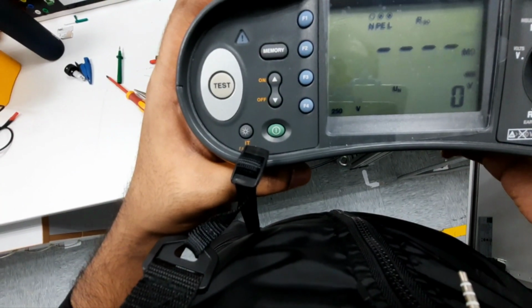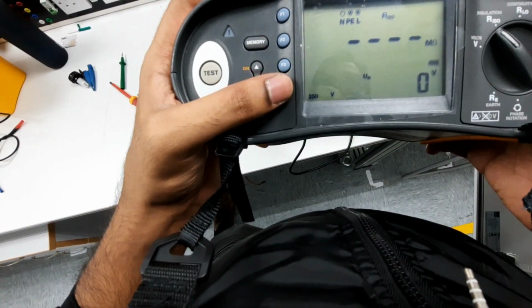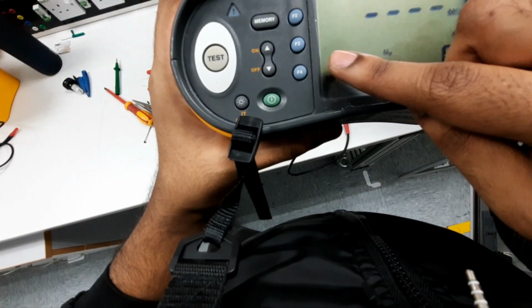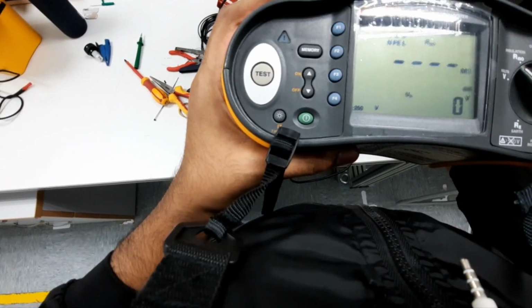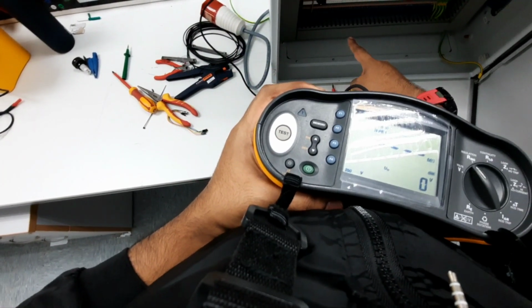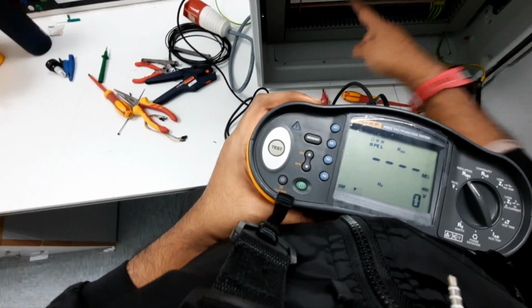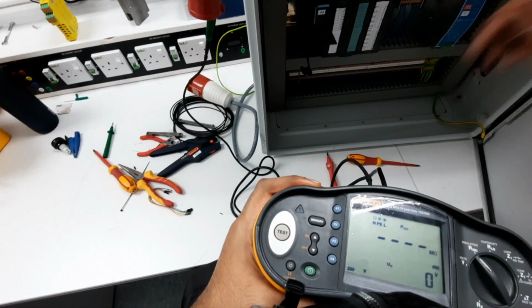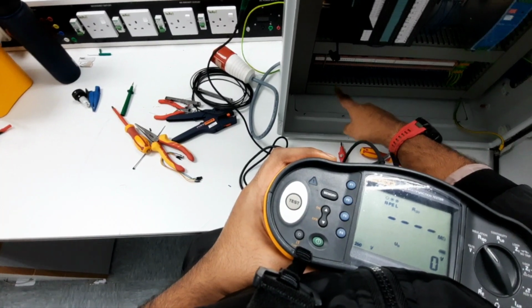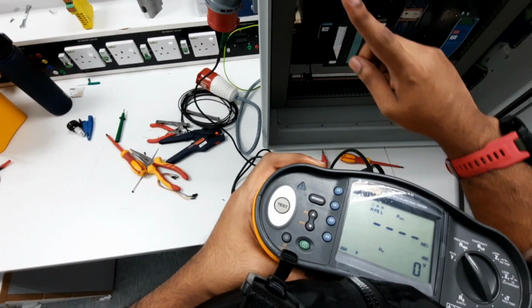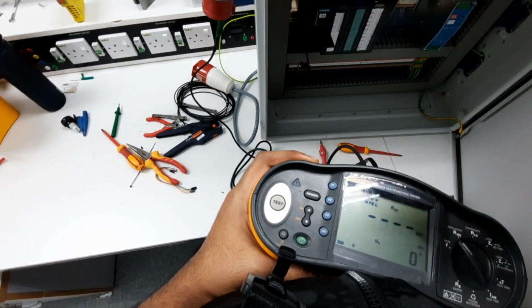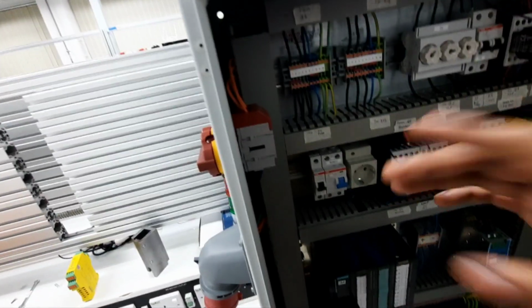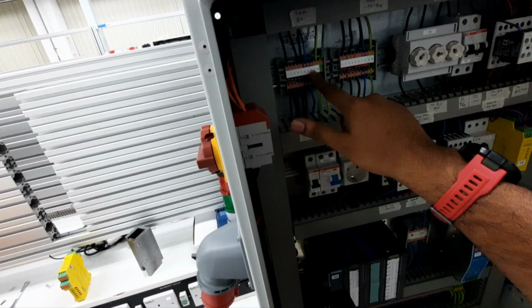So the first thing, you need to set this to 500. The 250 setting is actually for the 24 volt part down there, but we're not going to test that because it's not in the staging list. So we're only going to test line 1, line 2, line 3, and neutral.